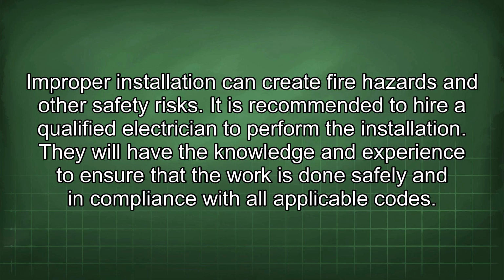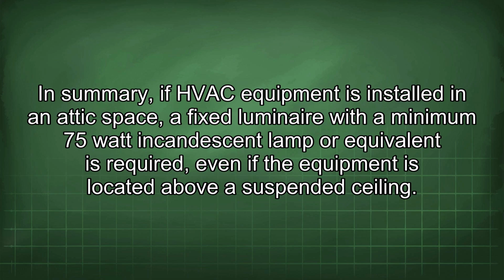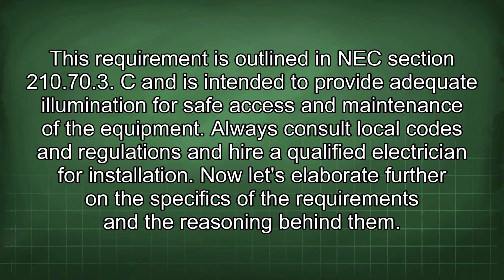They will have the knowledge and experience to ensure that the work is done safely and in compliance with all applicable codes. In summary, if HVAC equipment is installed in an attic space, a fixed luminaire with a minimum 75-watt incandescent lamp or equivalent is required, even if the equipment is located above a suspended ceiling. This requirement is outlined in NEC Section 210.70.3.C. It is intended to provide adequate illumination for safe access and maintenance of the equipment. Always consult local codes and regulations and hire a qualified electrician for installation.